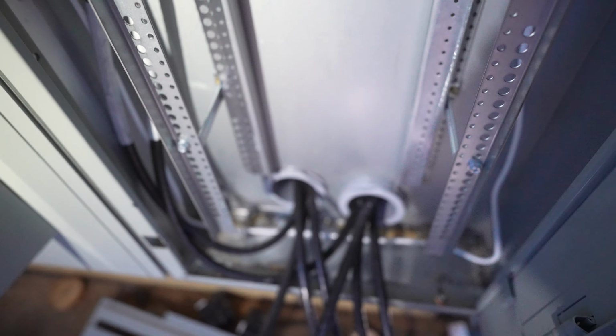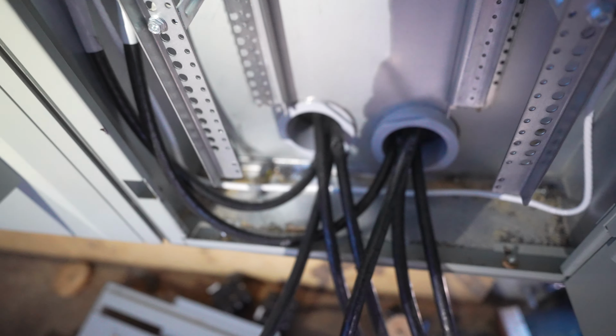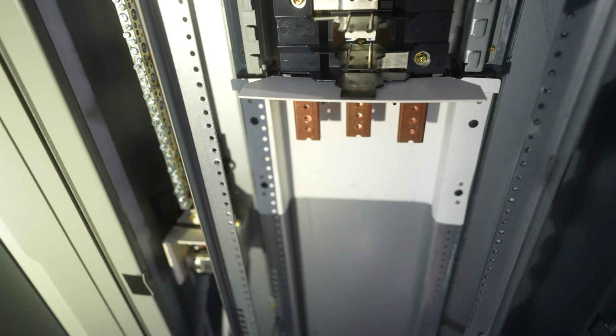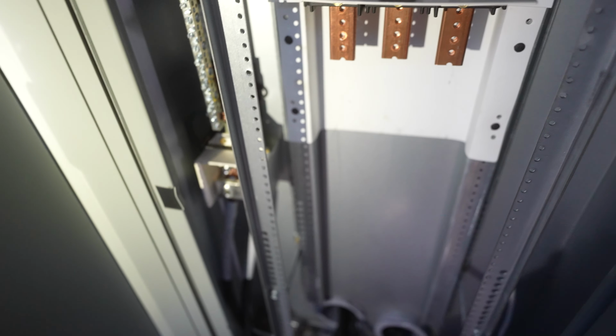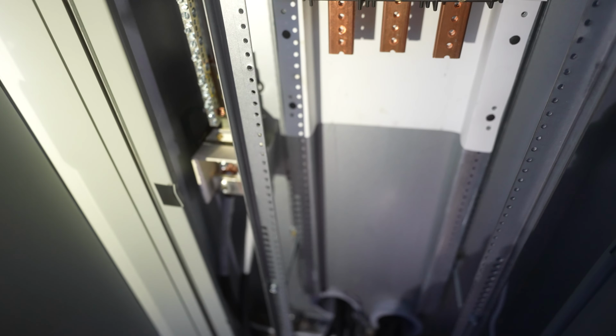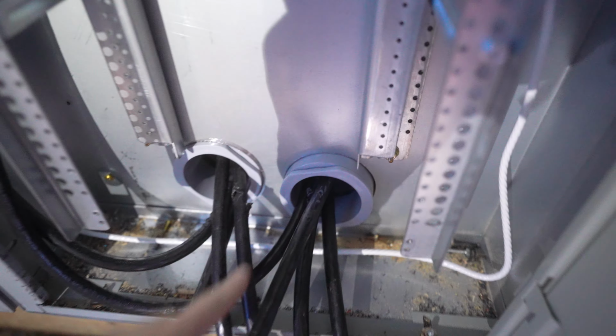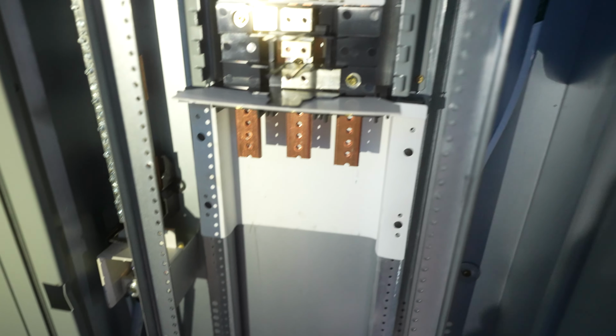Anyway, to show you guys the neutral here. We got 2 coming in because we're doing a parallel run, which means that we are running 2 sets of copper coming into each panel. This saves on the cost for the conduit, or for the actual wire. It's cheaper to run 2 parallel runs than to buy a lot thicker copper and then run that. It's cheaper per foot, cheaper to do. It's cheaper to just buy the plastic conduit and put 2 parallel runs in it. So you can see we have those 2 runs, run number 1, run number 2, and each one has 4 coppers coming in, 4-aught actually.